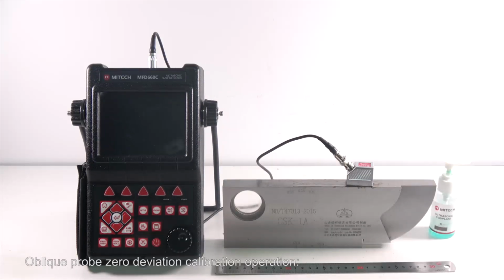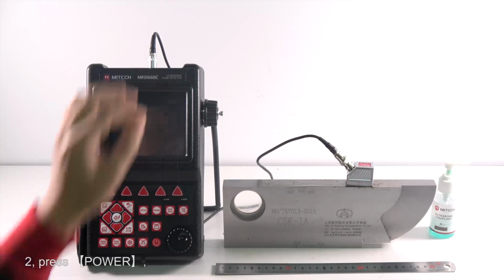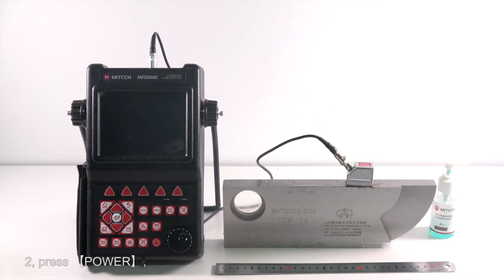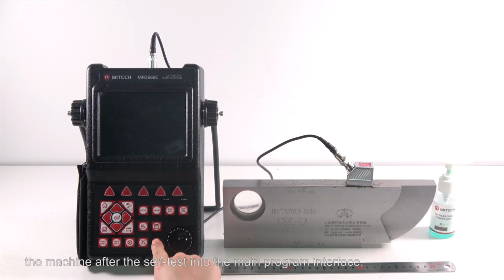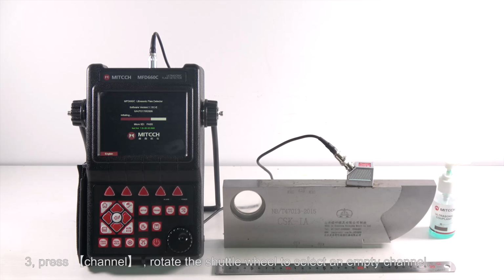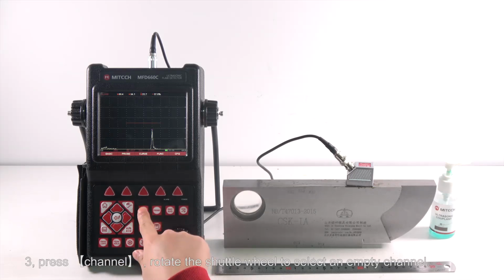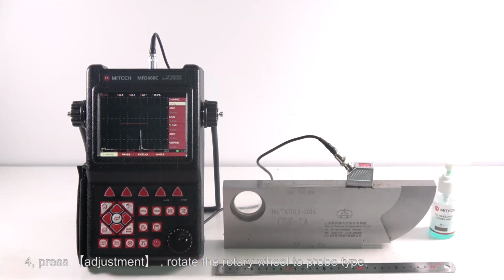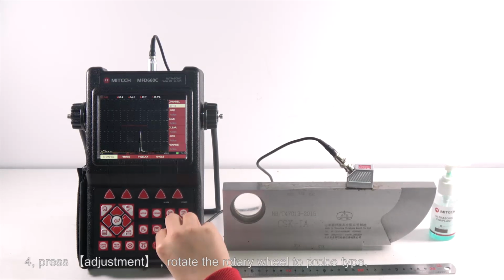Oblique probe zero deviation calibration operation. Connect the MFD660C main unit to the oblique probe. Press power. After the self-test, the machine enters the main program interface. Press channel, rotate the wheel to select an empty channel. Press adjustment, rotate the rotary wheel to probe type.